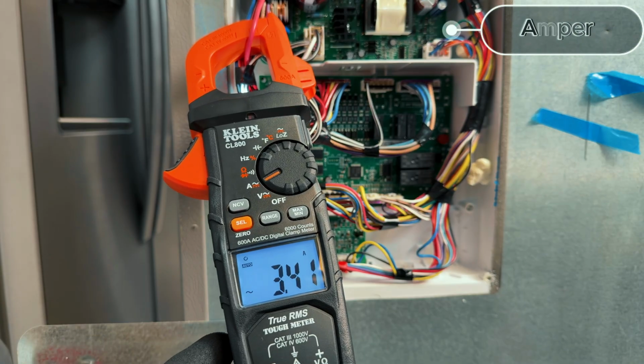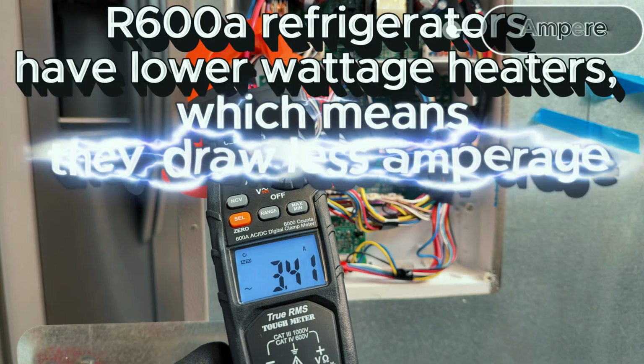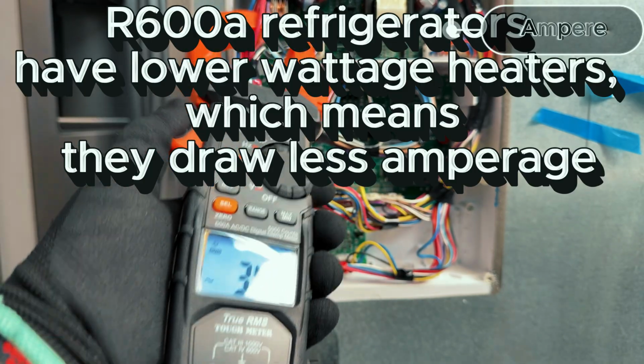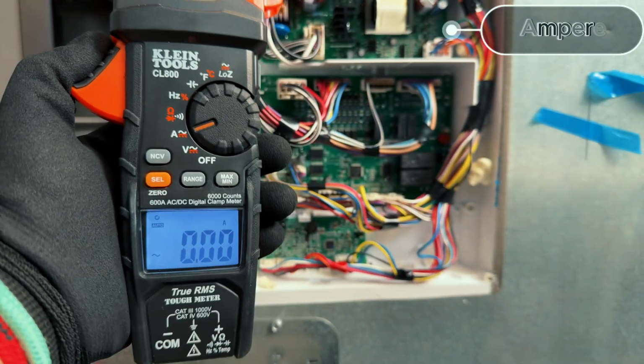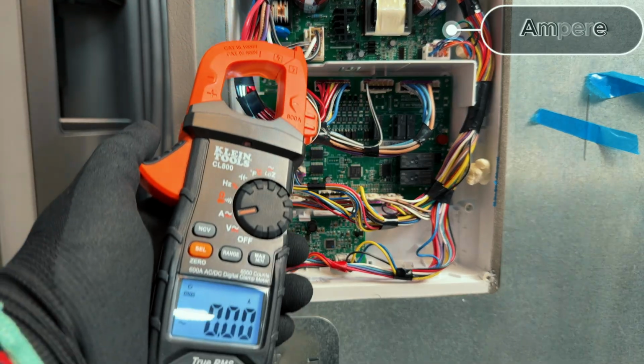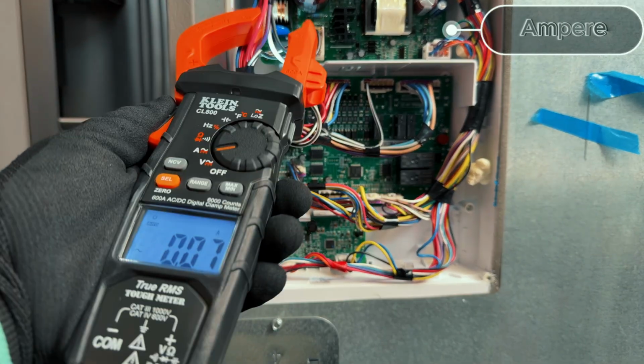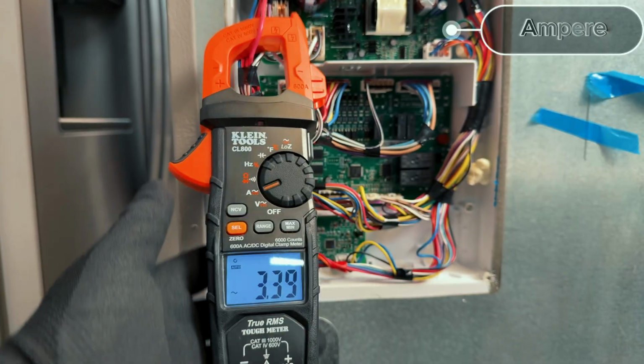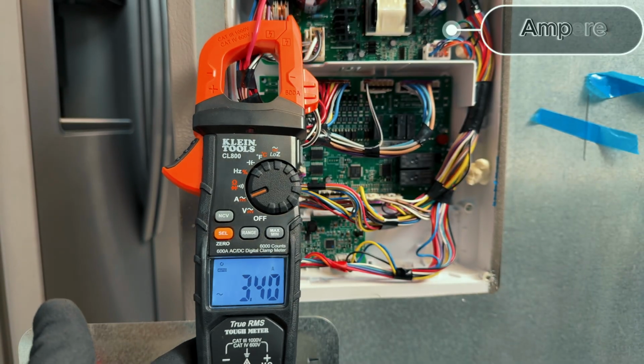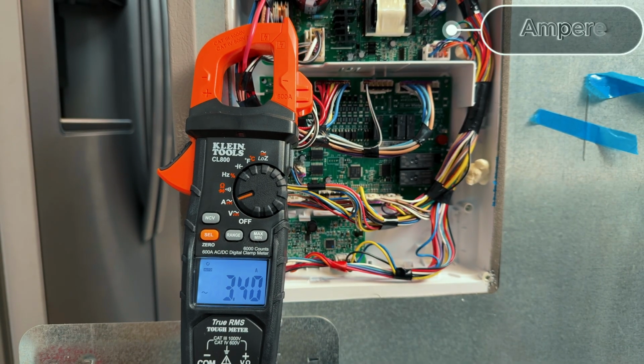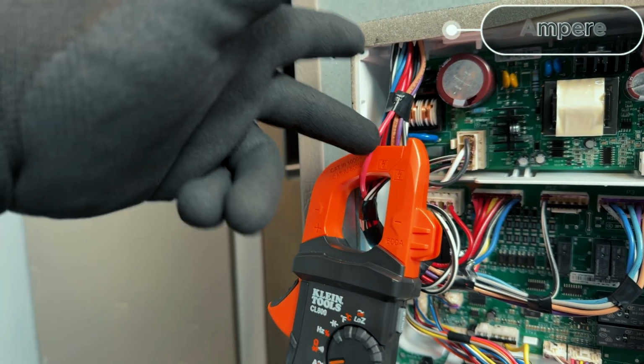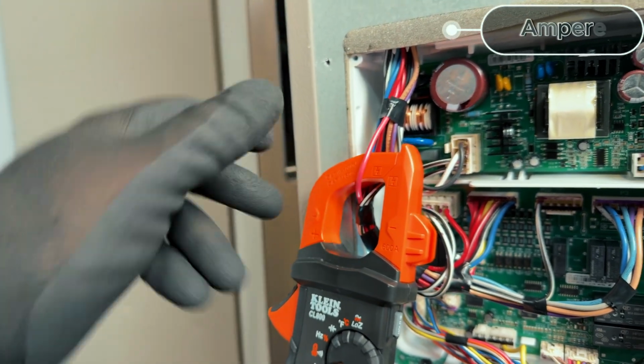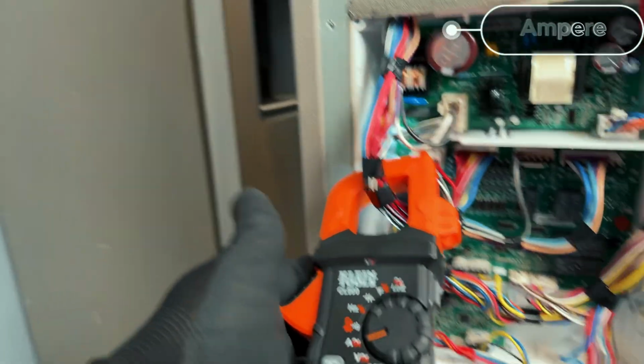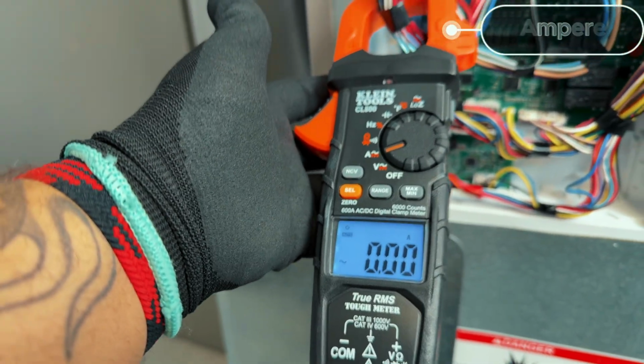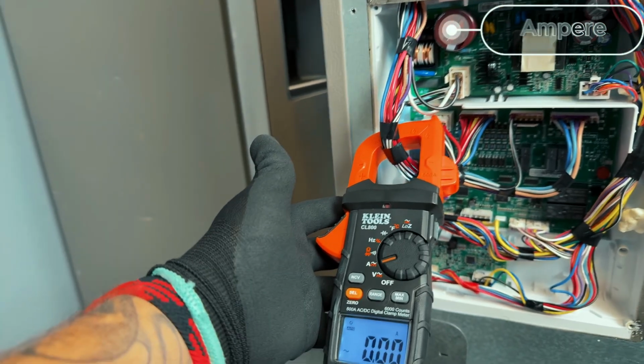Alright, so the heater's on. You can see I'm pulling about 3.4 amps. If I take it off, you can see I'm not getting anything. If I clamp it on the wire, there it is. I'm getting my amp draw. And like I stated, you only want to be on one wire. You're not going to get anything if you do the whole harness. As you can see, I'm doing the full harness here, and I'm not getting anything. It's just not going to be able to read.